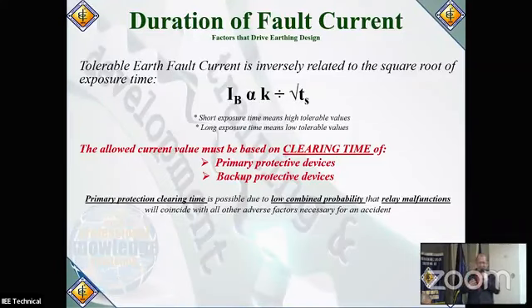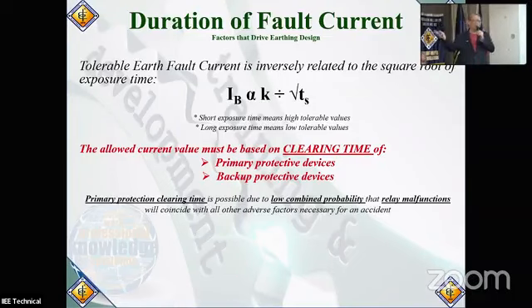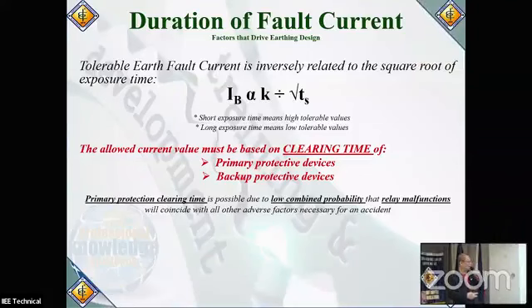Ano ang primary at secondary protection sa earth fault clearing? Tinatanong ko minsan, what's the difference between the 51N and the 50G sa mga sistema natin - yan ang primary at secondary protection. Ang 51N ay residually connected protection, earth fault protection, ground fault protection. Ang 50G naman ay zero sequence protection. Magkaiba yan - magkaibang CT ang gagamitin mo, magkaibang relay din.